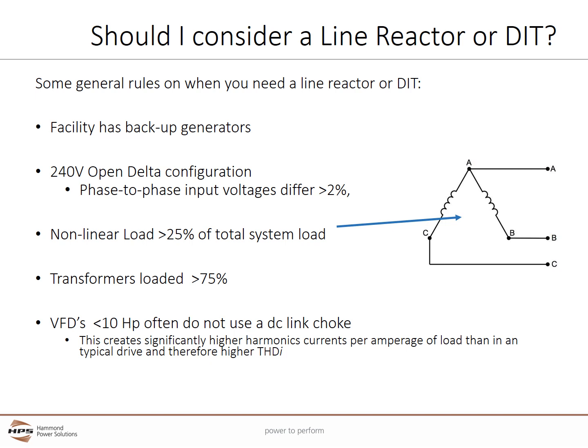In this DIT and line reactor application, we are talking about protecting the larger power transformers that would feed the overall circuit and power a number of devices, including the VFDs. Generally, VFDs below 10 horsepower and sometimes larger don't have DC link chokes. The absence of a DC link choke means these VFDs put out more harmonics per amp of load than other VFDs, and should therefore be strongly considered for line reactors, especially for facilities like warehouses where you may have many smaller VFDs installed.